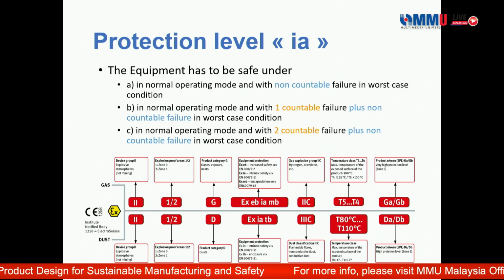Non-countable faults are things like shorting of ordinary components: resistors, transistors, traces of circuitry, wiring, and so on. The notified body has the right to short circuit or open circuit any part of your circuitry to form a non-countable fault.